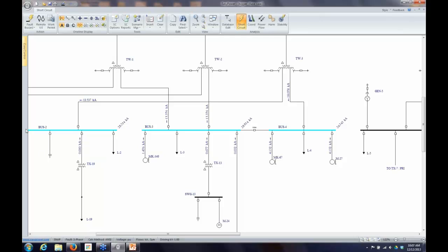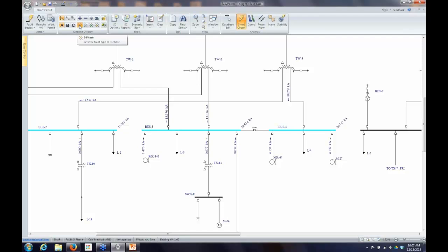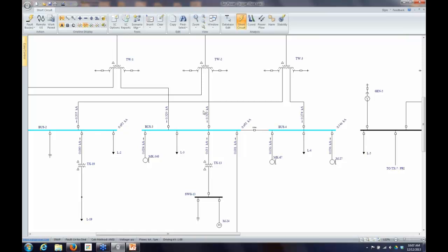Now let's look at some of the options available. On the screen, these controls determine what gets displayed and also what type of fault is going to be calculated. Starting down here, this button — which was the default — is the three-phase fault. If I select the next option, that's a line-to-ground fault. Clicking it reruns the calculation for those three buses as a line-to-ground fault, and you'll see the values are very low because we have resistance grounding on the neutrals.